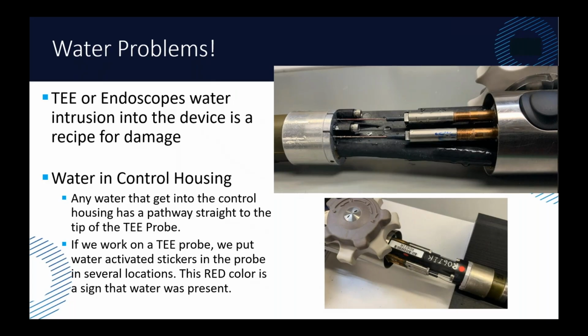So here's what happens when we see water inside articulation housings or articulation controls. And understand when a TEE probe heads to our facility, the first thing that happens is it goes in quarantine for 24 hours. So when we find actual water droplets, there was enough water in there to fend off evaporation for at least 48 hours because it had to be shipped. Sometimes that could even be longer than that. So that means there was significant water inside there at some point in time.